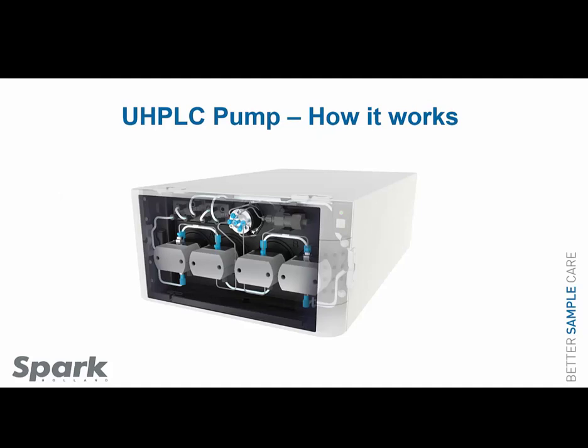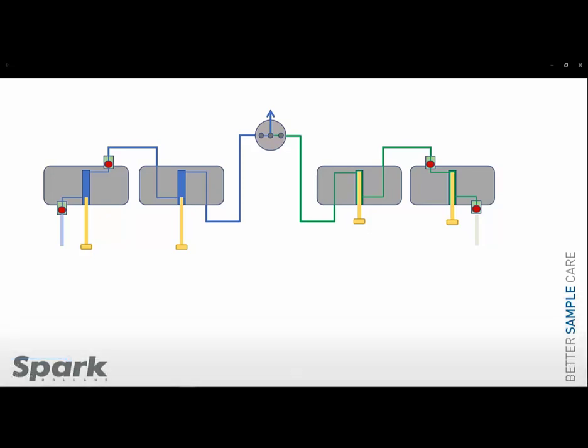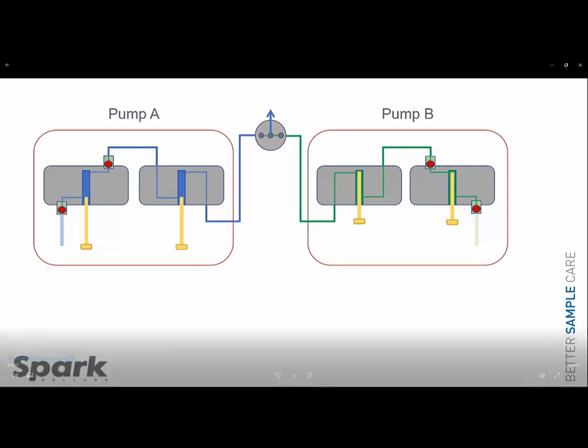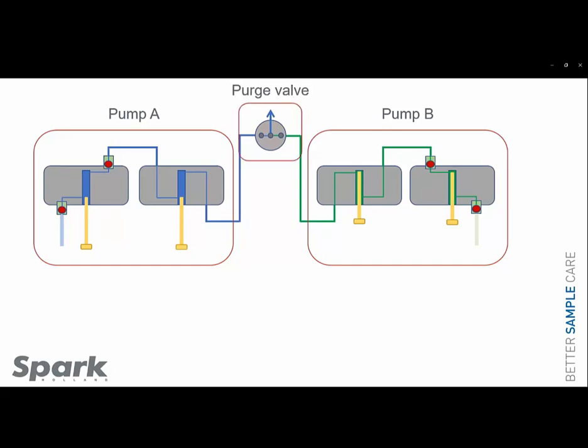Now we will continue with explaining how the UHPLC pump technology works. Pump contains 4 pump heads. 2 pump heads for pump A and 2 pump heads for pump B. With this you have a gradient set. Both pumps are connected to the purge valve.